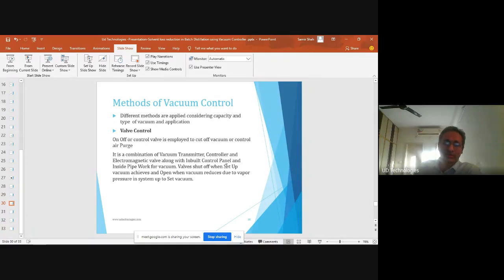So there are different methods of vacuum control. One is valve control. An on-off valve or control valve is employed to cut off vacuum or control the air purge. For example, you have to apply a lower vacuum like 500 mmHg. One on-off valve will cut off when 500 mmHg is reached and open when the vacuum absolute pressure increases.